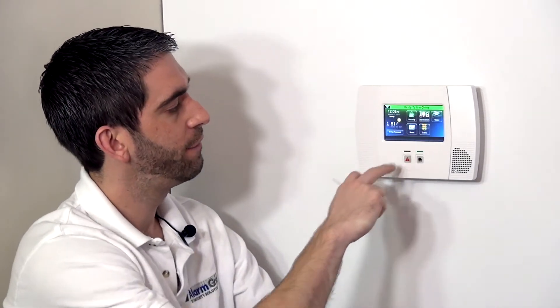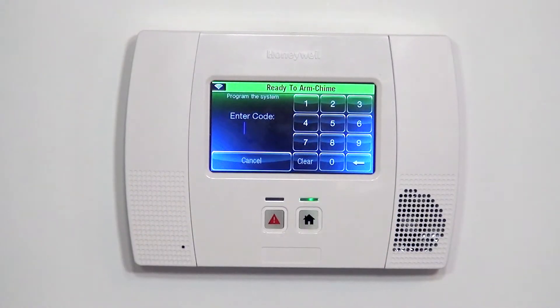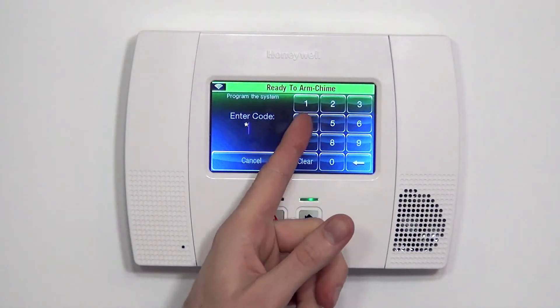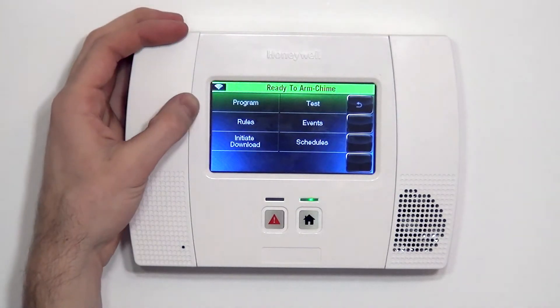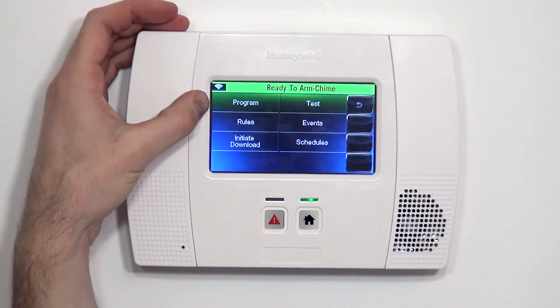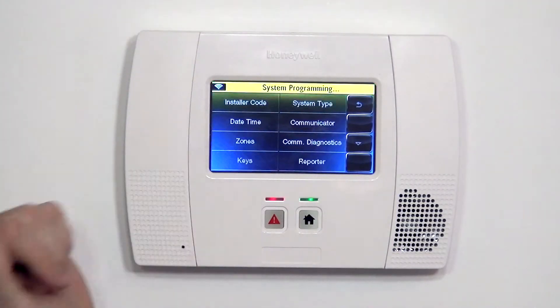The first thing we do from the home screen is hit Security, then More, and Tools. From Tools, we use 4112, which is the default installer code, and gets us to this screen where we can select Program to jump into System Programming. As soon as we hit Program, it says System Programming, letting us know we're now in Programming.